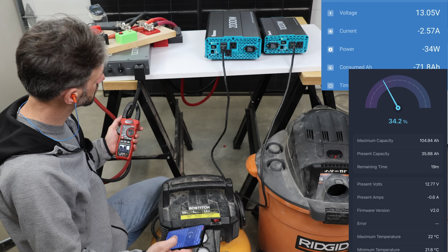All right, we were at 230 amps with the clamp meter. I don't know if you could see that on the screen or not. The Victron shunt was showing a little less than that, but either way we were well over the 200 amp continuous running max for the battery BMS. I think with the compressor running and starting up the shop vac, that surge current, which is really high, tripped the BMS because everything shut down for a second, but then it came back on and kicked them both on at the same time and ran them continuously.